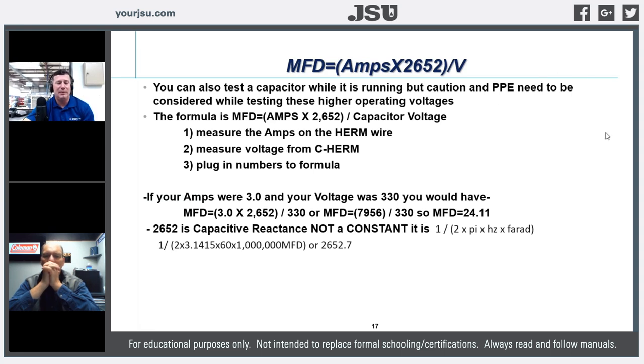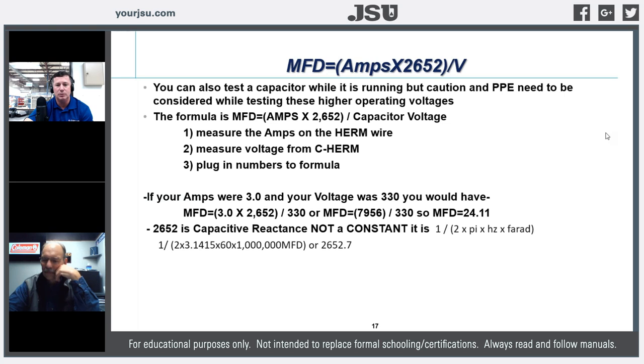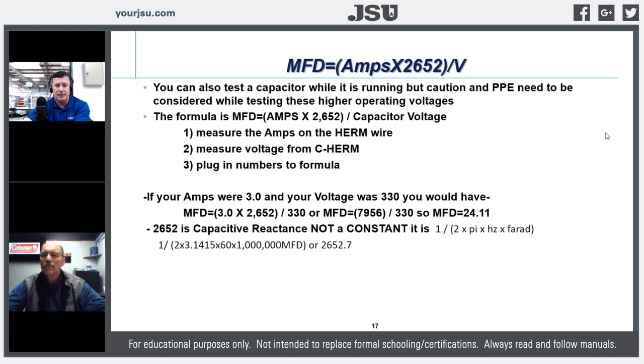One thing I found in the field is a capacitance load test — testing the capacitance rating of a capacitor while it's running. The formula is: microfarads equal amps times 2652, divided by the actual capacitor voltage. That 2652 factor is based on the 60-cycle rate in the United States. The 2652 number is different if you're working in countries that use 50 hertz.